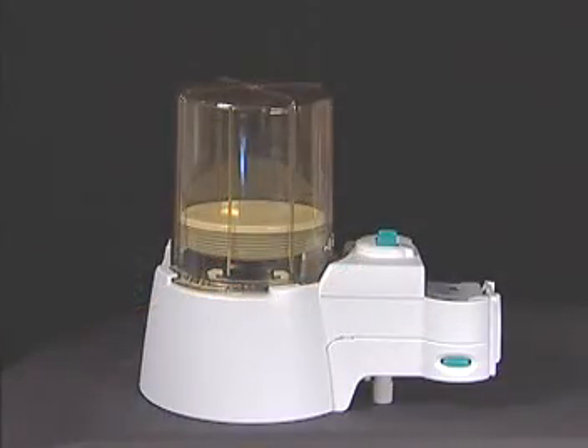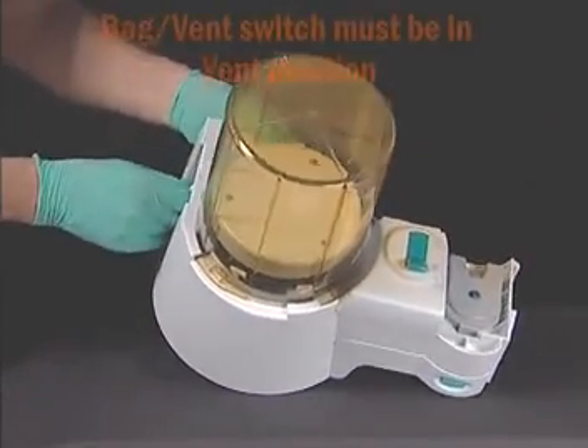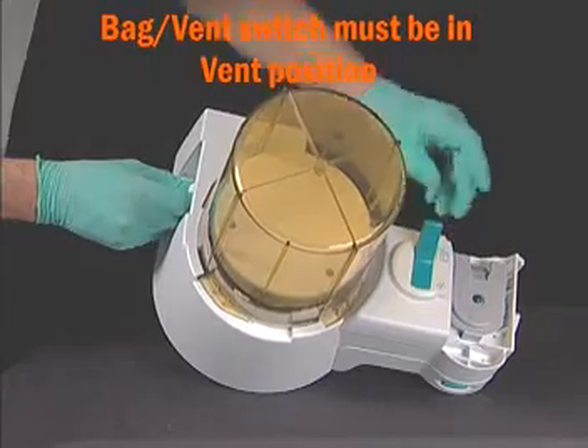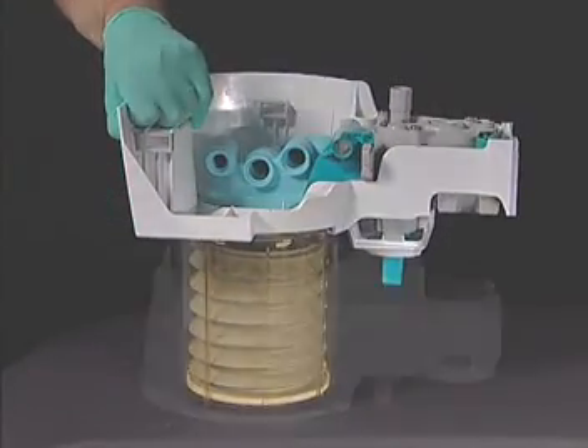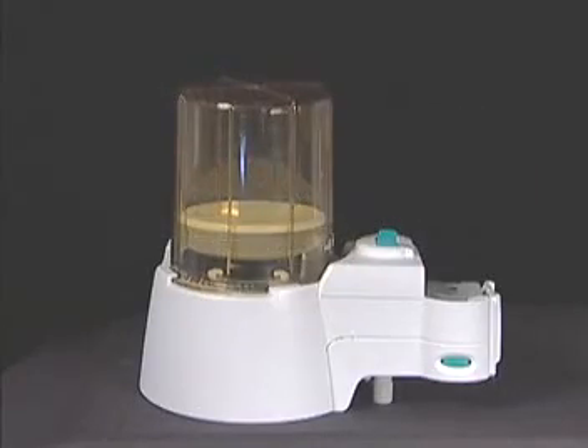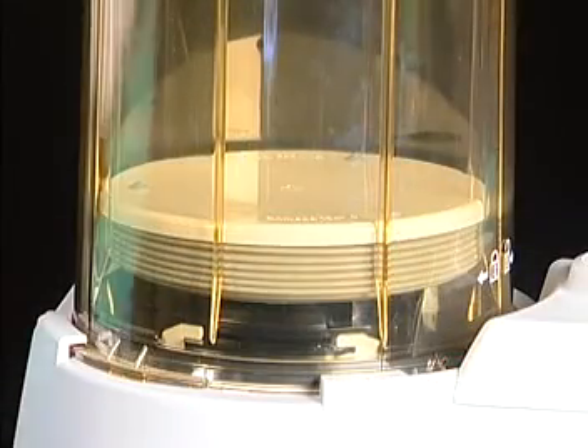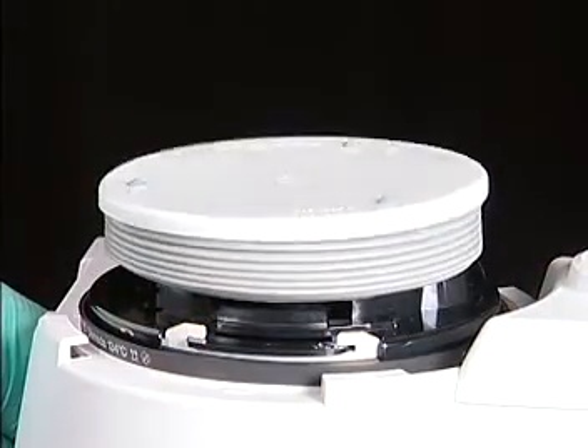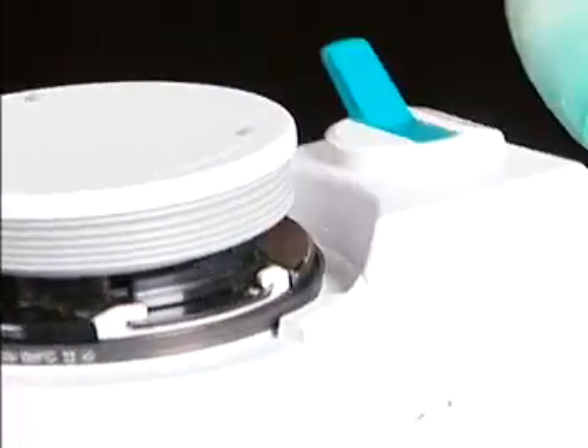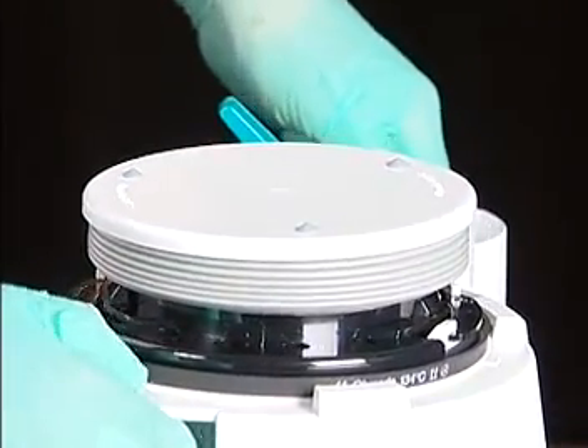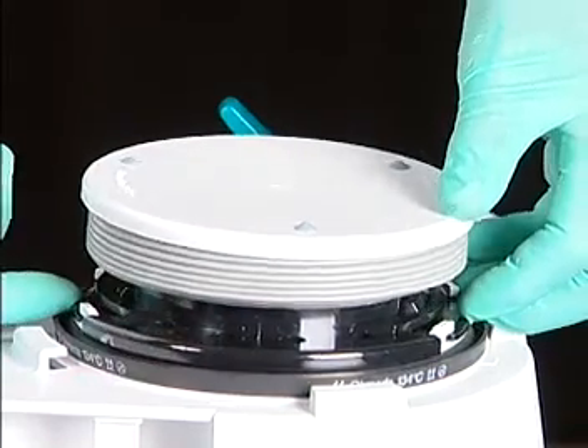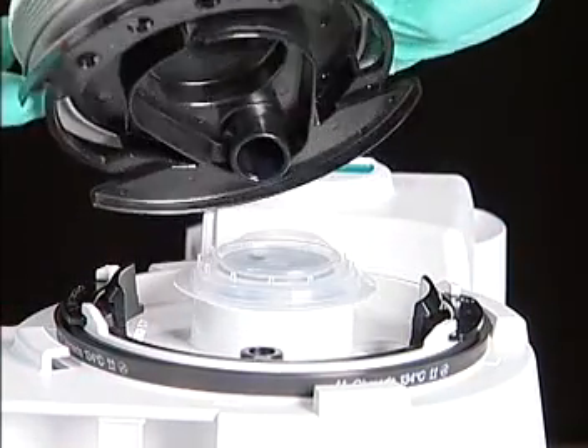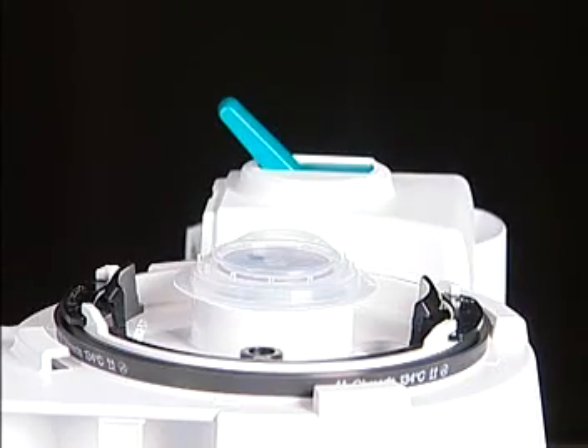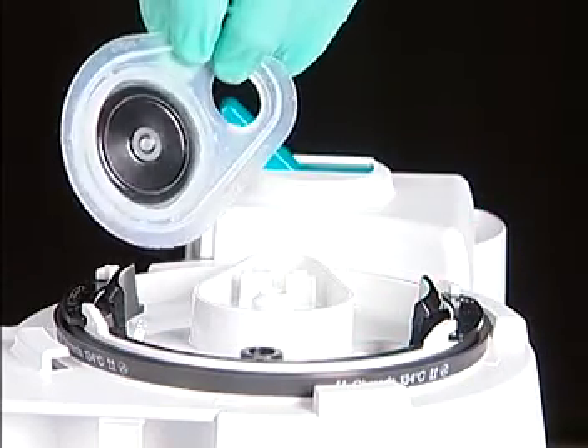The bellows and bellows canister can be autoclaved while attached to the ABS bellows base. Place upside down so that the bellows is completely extended. Should you wish to disassemble the bellows, turn the bellows canister counterclockwise and remove. Then squeeze the locking ring on two sides to release the bellows. Finally, remove the valve under the bellows.